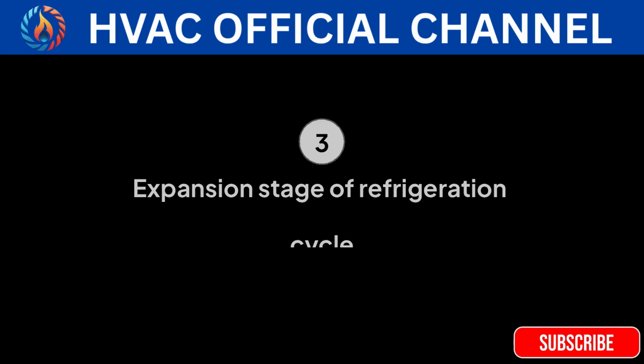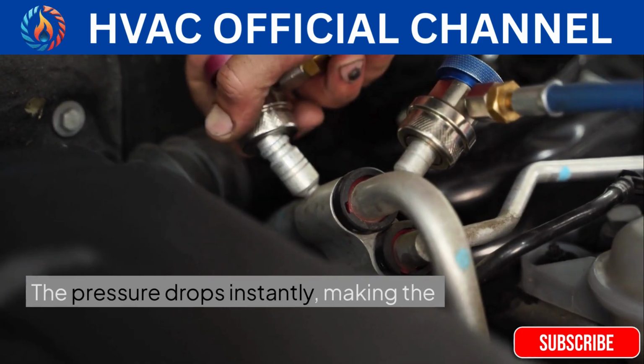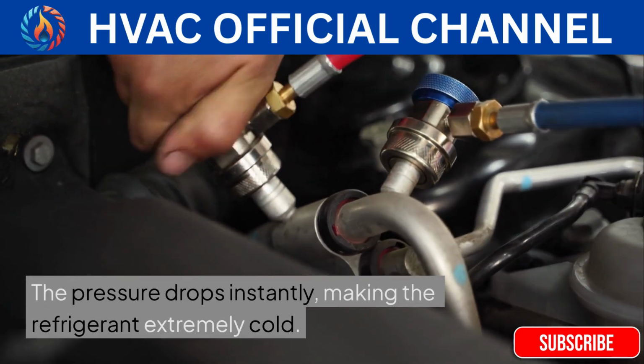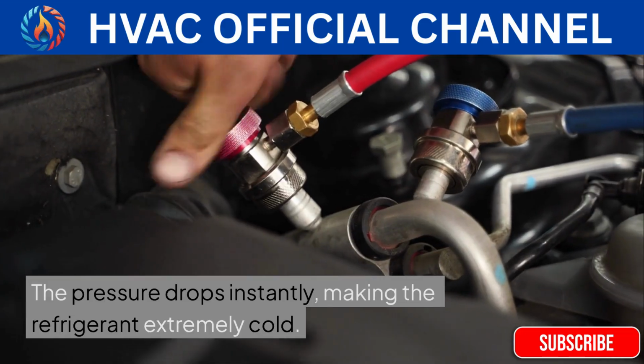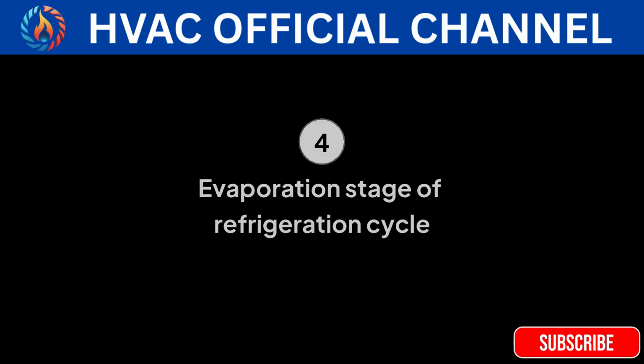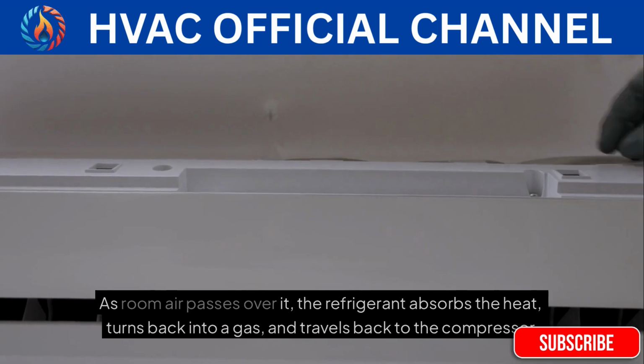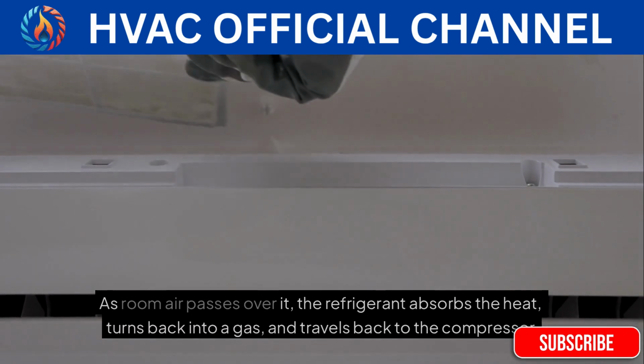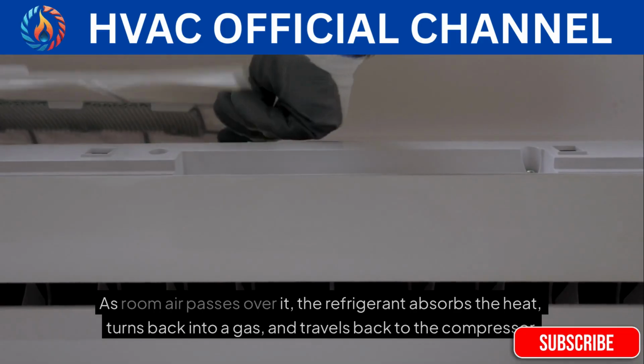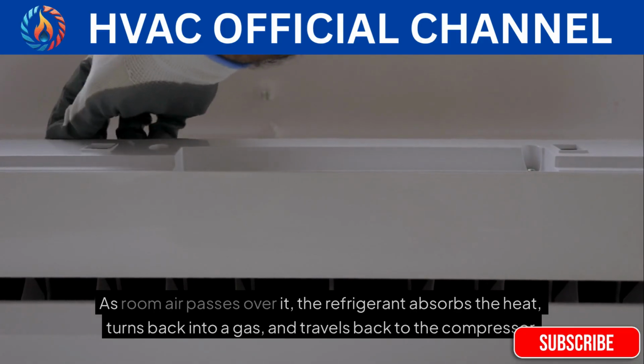Expansion. The high-pressure liquid passes through a capillary tube or expansion valve. The pressure drops instantly, making the refrigerant extremely cold. Evaporation. This cold liquid enters the indoor unit. As room air passes over it, the refrigerant absorbs the heat, turns back into a gas, and travels back to the compressor to start again.